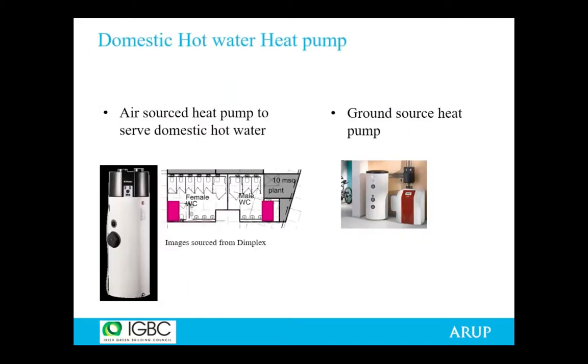And another thing, domestic hot water is often produced as well now by air source heat pumps, and generally the domestic hot water production is separated from heating production, and that's because domestic hot water tends to be at about 60 degrees centigrade for Legionella control, and so the heat pump to deliver that high temperature heat is not going to work as efficiently as it might for delivering space heating, where you can deliver it at, say, 30 or 40 degrees centigrade. So it's good to separate those two cycles so that you're getting the best efficiency from the heat pump when you only need it for heating.